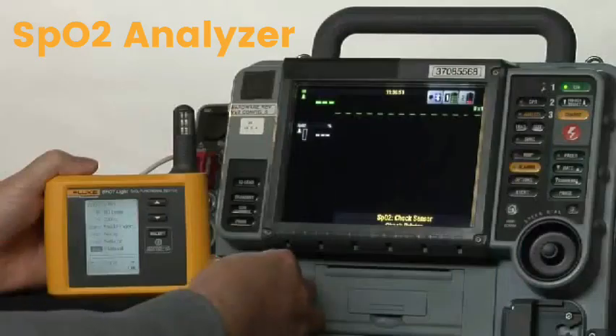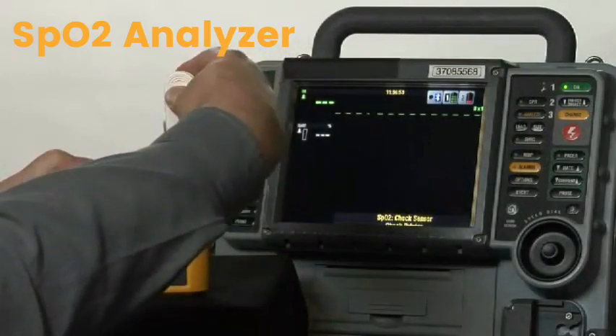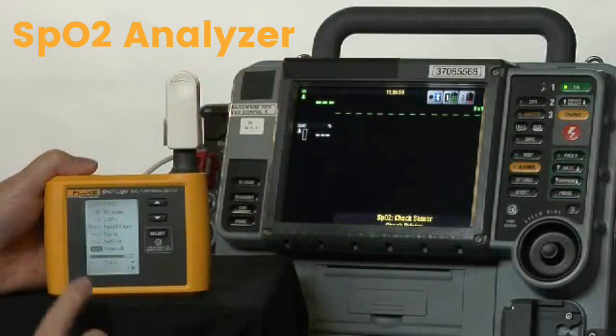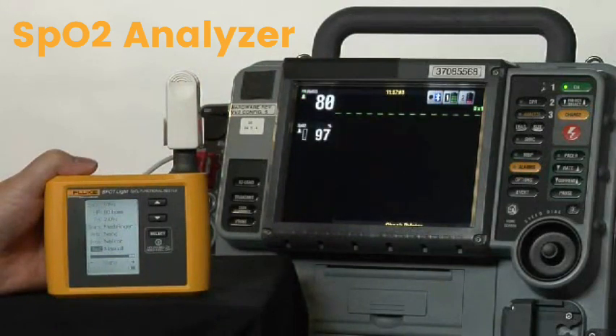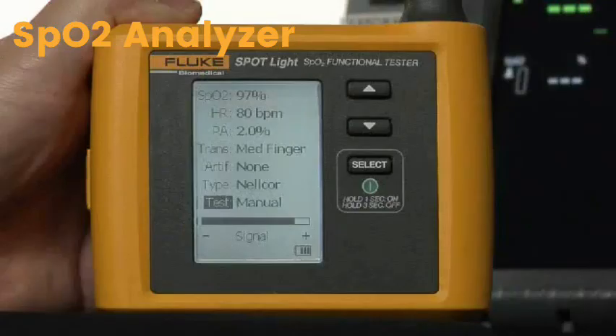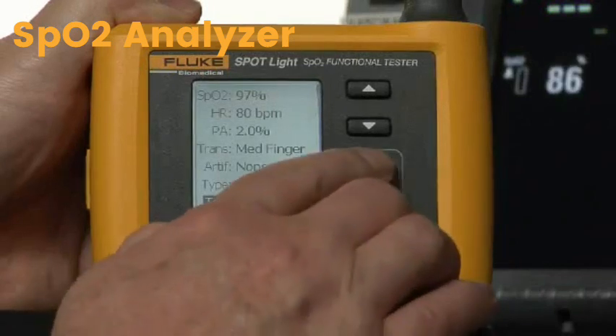And we will then connect the oximeter sensor from the medical device. And we'll watch this bar down at the bottom. It's called the signal strength bar. You can see that it has a good signal, and you will begin to see the display on the screen of the defibrillator. Now, testing this functionally really quickly is just a 4-button push.